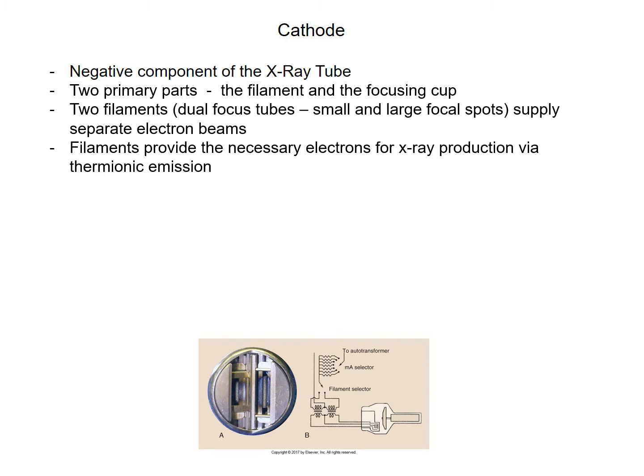And of course, we'll talk about this in our next unit, how X-rays are created. We'll review that. But remember, when the electrons strike the anode, two processes by which X-rays are created, either Bremsstrahlung or characteristic. We want to keep in mind that the filaments are made out of what we call thoriated tungsten, as opposed to the anode where you've got tungsten rhenium. So the filament is thoriated tungsten.